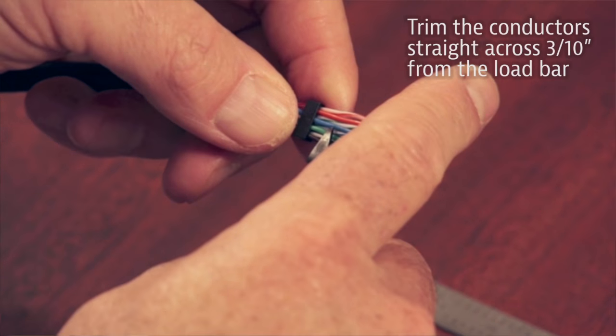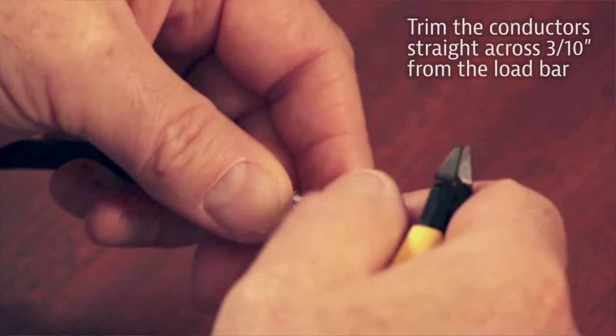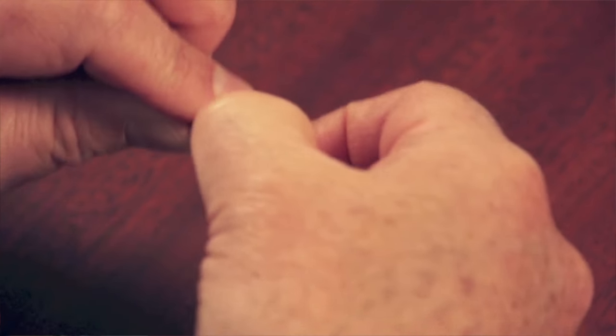The next step is to trim the conductors. From the fully seated load bar, I want to measure three tenths of an inch and trim off my conductors approximately three tenths of an inch. I'm holding my finger over the exposed conductors so they don't fly off. You want to make this nice and straight with no angle. Your load bar does move a little bit, so reposition it back in. Now I'm ready to insert this into the actual connector.